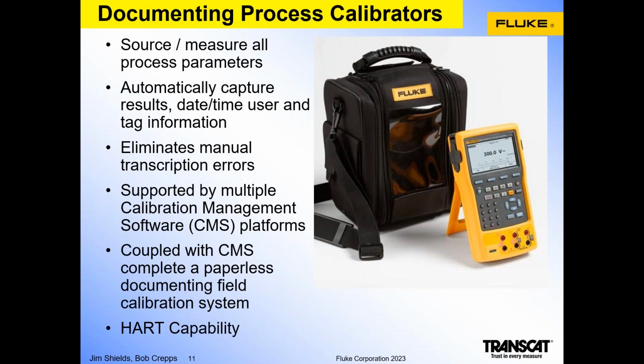So one of the elements of this process that I mentioned is the Documenting Process Calibrator. There's a variety of different manufacturers of documenting process calibrators. Of course, I'm showing the Fluke one. This is the Fluke 754. It will source and measure virtually all critical process parameters for instrumentation. It automatically captures results, the date, the time, the user, and the tag information. And since it automatically documents and there's no writing on a clipboard, for example, it eliminates manual transcription errors.